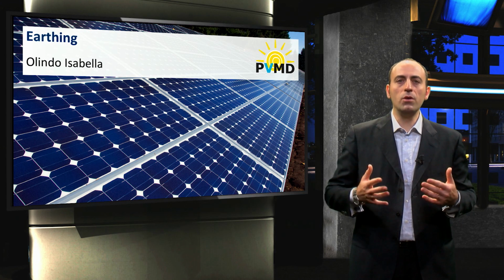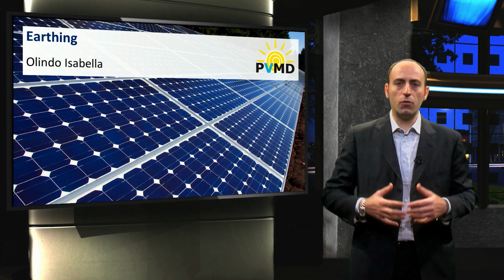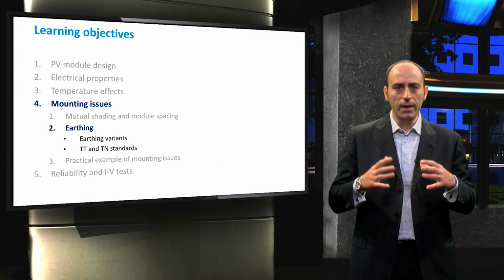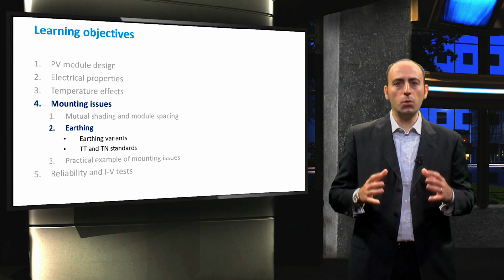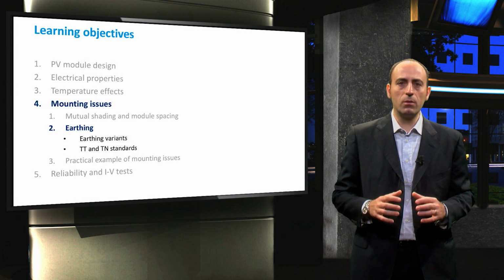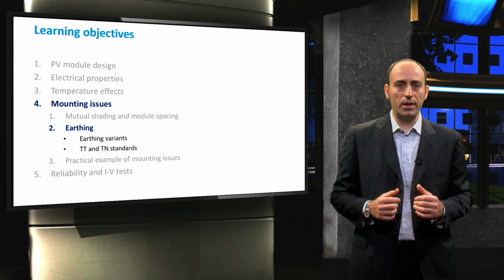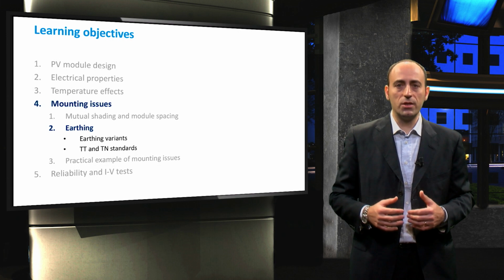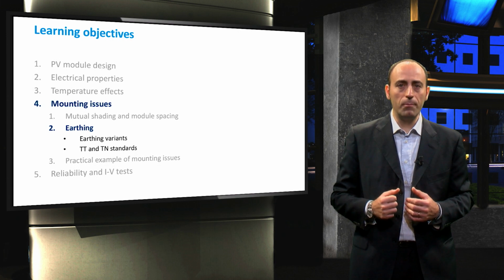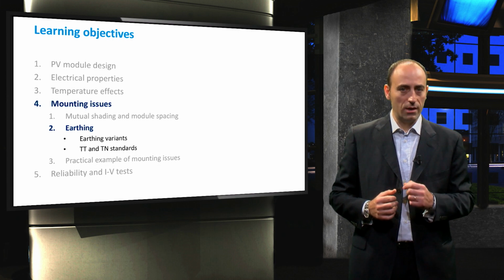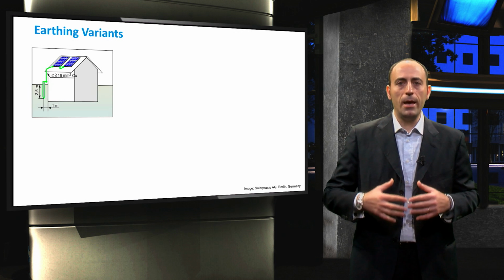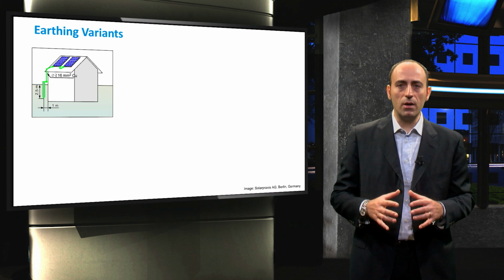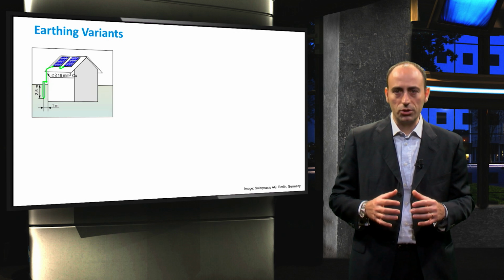In this video, we are going to talk about the earthing options for PV systems. The essence of earthing is to ensure that all parts of the building which could become charged are maintained at or near earth potential. Otherwise, phenomena such as potential-induced degradation might happen or safety issues may arise. By law, a PV system has to be connected to the ground circuit of the building or construction.